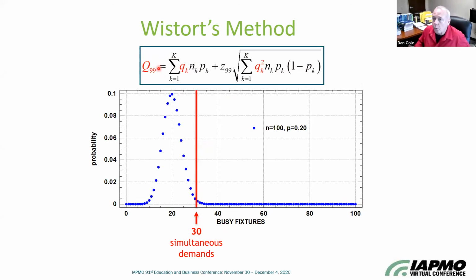You wouldn't have to work with the fixture units. You wouldn't have to work with the curve. This would automatically compute the 99th percentile flow rate for all these given fixtures. What this is called in statistics is a normal approximation to the binomial distribution. The binomial distribution is a set of discrete individual points. A normal approximation is a continuous curve connecting all the points.